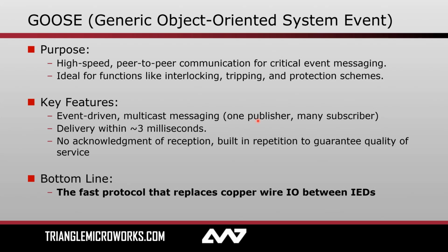So GOOSE is going to be the high speed and crucially peer-to-peer communication that's used for critical event messages. And this is ideal for things like interlocking, tripping, and protection schemes. So it is event-driven all the time, unlike reports where we have the option to issue reads or cyclic reports, things like that. GOOSE is always event-driven. In fact, it's always being published. There's no acknowledgement of reception within GOOSE. It is a layer 2 protocol. You can think of it similar to maybe UDP, if you're familiar with that. But there are other built-in mechanisms to guarantee quality of service, namely the fact that it's repeated. And I'll get into exactly how that works here in a couple slides.